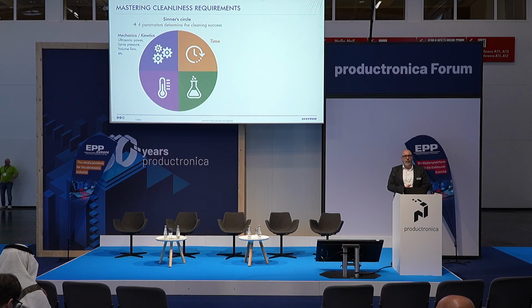Then the time, so how long a cleaning or rinsing process is running. The temperature. This is very basic physics: the higher the temperature, the faster a chemical reaction happens. But there are also downsides, because materials can be sensitive to high temperatures, so this needs to be balanced. And then, of course, very important, what kind of chemistry are you using in your process? Because that depends a lot on the contaminations that you have to remove, and also the materials on the system, so that they are compatible and not damaged.